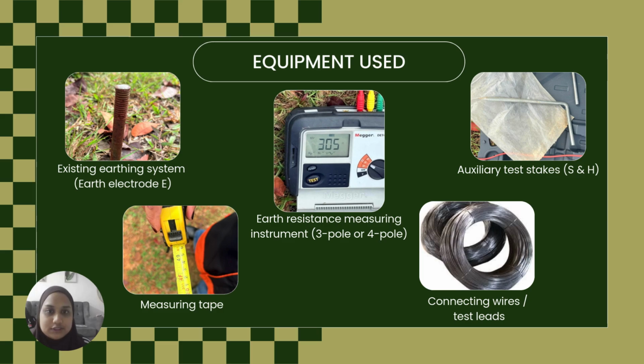So now this is our equipment used. We have five pieces of equipment for this lab. Number one is the existing earthing system, earth electrode E. The second one is the earth resistance measuring instrument with three pole or four pole. And then auxiliary test stakes, connecting wires or test leads. And the last one is the measuring tape.